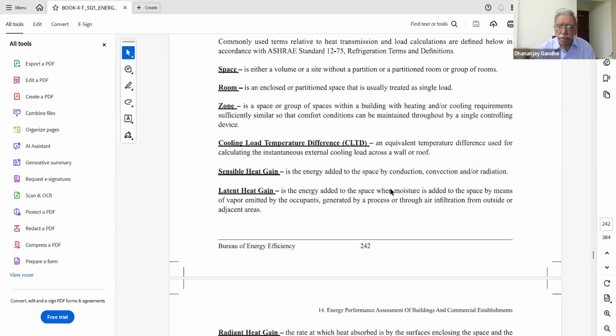Then there is sensible heat gain. That means heat coming from outside by conduction, convection, or radiation from various sources. It is sensible heat gain, which goes into increasing the temperature of the atmosphere within the building. Then there are certain loads where the heat does not increase the temperature within the atmosphere, but the moisture that is present in the room gets heated up by outside air. So it also constitutes a certain load, and moisture can also come from the people working there, who produce some moisture through their breathing.